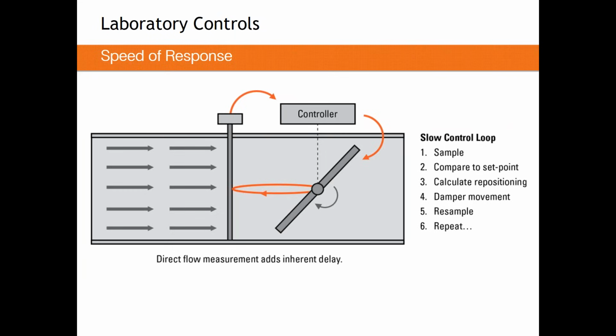If you're a manufacturer of only closed loop styles of devices, you need to make those closed loop devices look like a Venturi valve. Remember, Venturi valves can be advertised as instantaneous speeds of response due to that second definition we gave. So if you need to make a high accuracy terminal compete with that, what you can say is they have a high speed of response to a control signal.